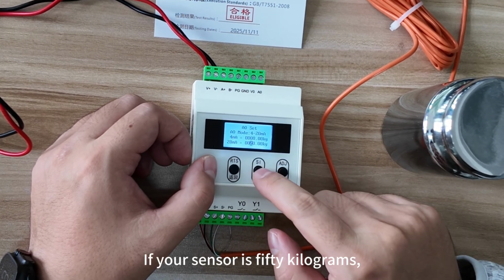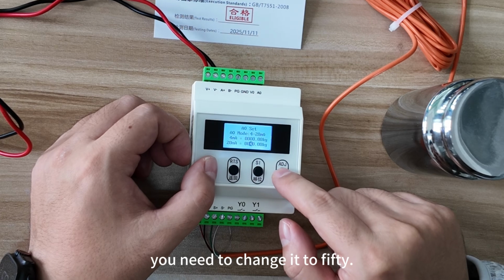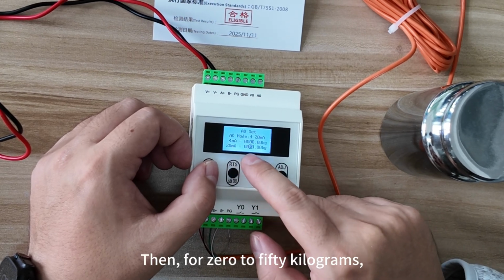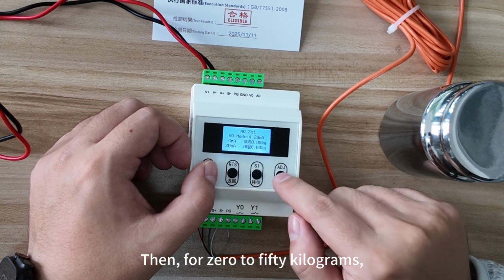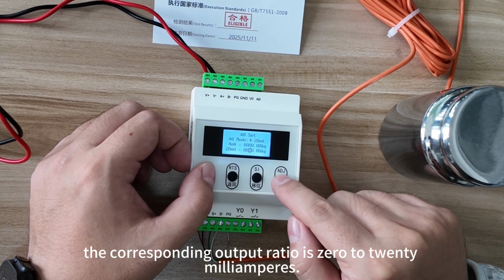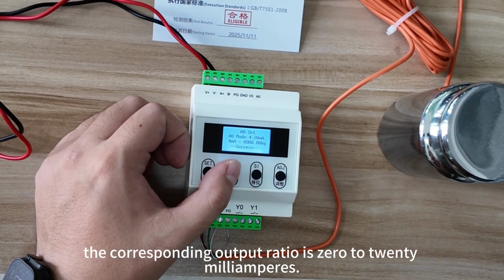If your sensor is 50 kilograms, you need to change it to 50. Then, for 0 to 50 kilograms, the corresponding output ratio is 4 to 20 milliamperes.